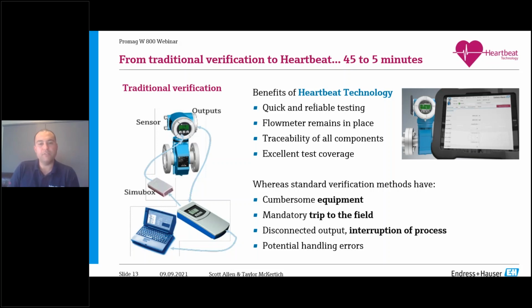These days with heartbeat verification, we're talking about verification that can be done in as little as 5 minutes, and in some cases even quicker. We don't need any tools anymore. With the W800, for example, it can even be done remotely over cellular if that's a requirement, so even going to the field may not be necessary. It can be done without interrupting the process as well. It's quite an advancement in how verification of flowmetering can be done.